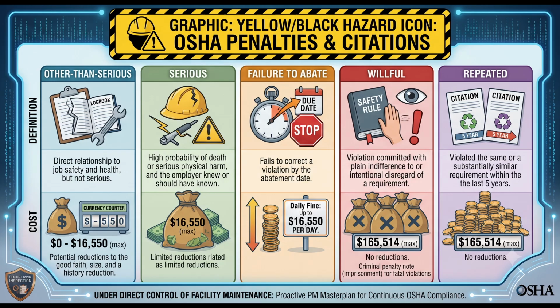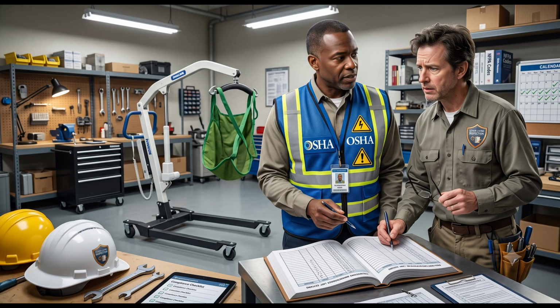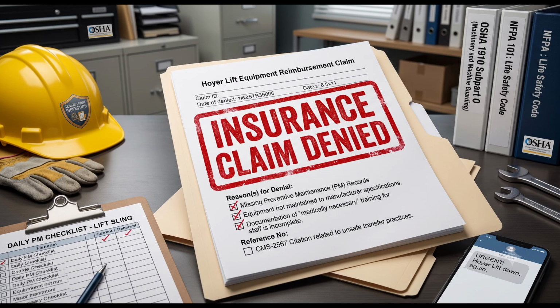Then there's OSHA. If a care aide injures their back while using a resident lift that had a skipped mechanical inspection, OSHA doesn't just look at the injury. They demand the PM history for that piece of equipment. If you can't produce a documented maintenance log, that single incident escalates from a basic workers' comp claim into a serious or willful OSHA violation. Serious violations carry thousands of dollars in penalties per occurrence. And a willful violation, where they prove you knew the equipment needed servicing and ignored it, can run over $150,000 per violation. But the fun bus hasn't completely left the parking lot yet.